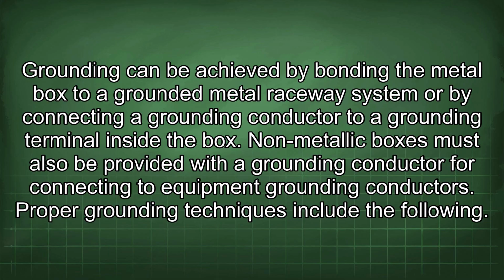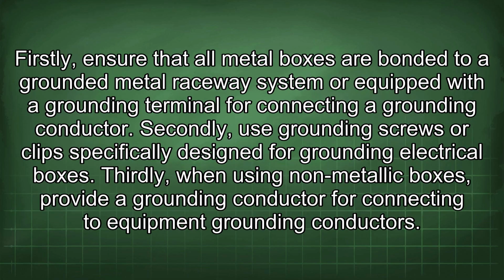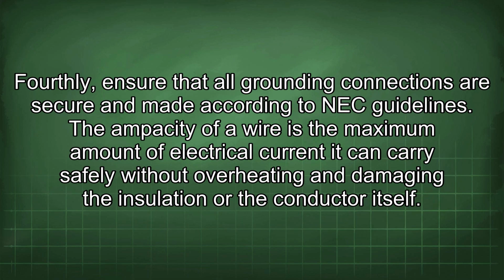Proper grounding techniques include the following. Firstly, ensure that all metal boxes are bonded to a grounded metal raceway system or equipped with a grounding terminal for connecting a grounding conductor. Secondly, use grounding screws or clips specifically designed for grounding electrical boxes. Thirdly, when using non-metallic boxes, provide a grounding conductor for connecting to equipment grounding conductors. Fourthly, ensure that all grounding connections are secure and made according to NEC guidelines.